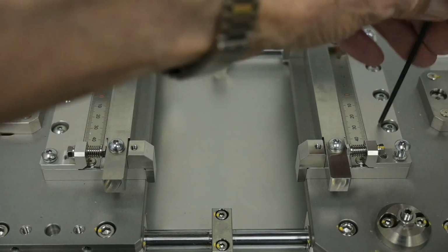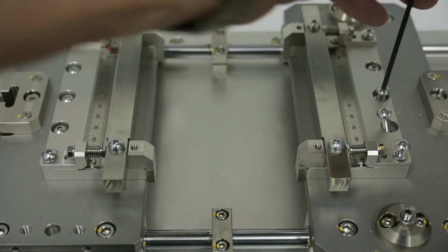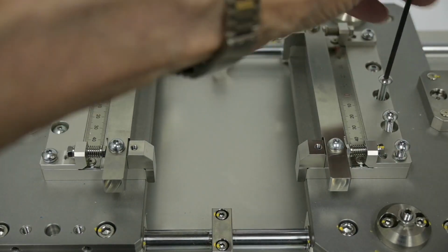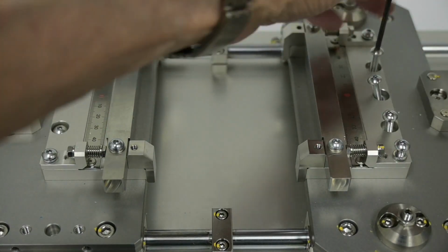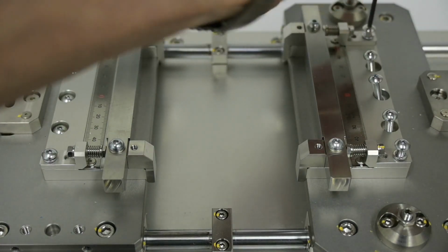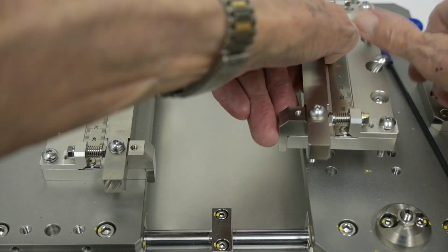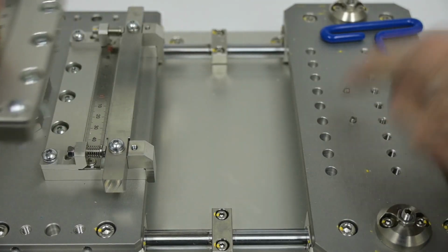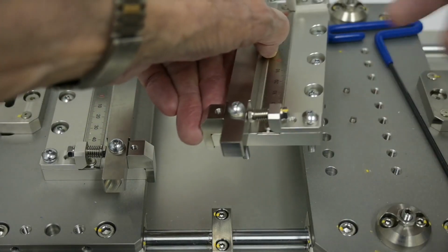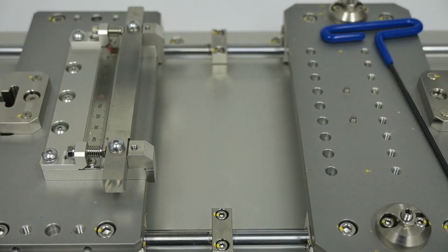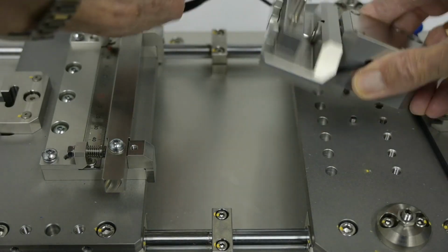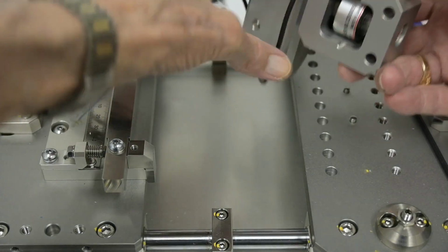First, I will remove the fixed clamp, loosening 5 screws. Lift it off, making sure you don't lose the screws. Notice the 2 pins. The clamp has 2 holes to align properly. Install the load cell clamp. These 2 holes in the bottom will align with the 2 pins.